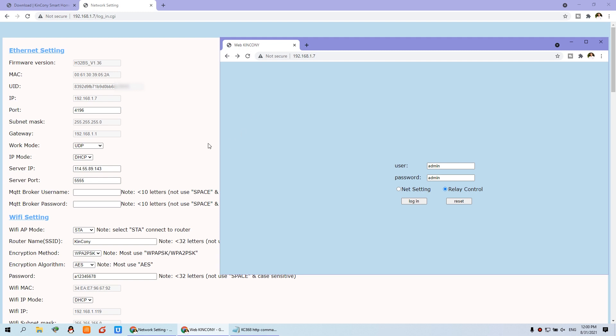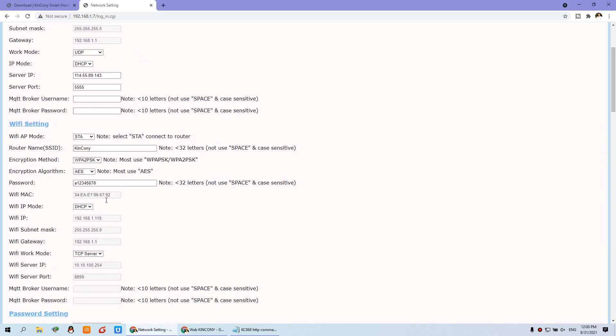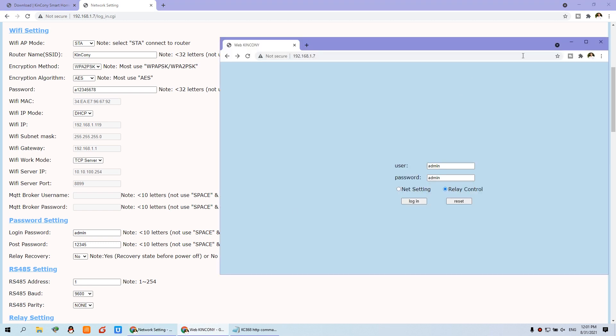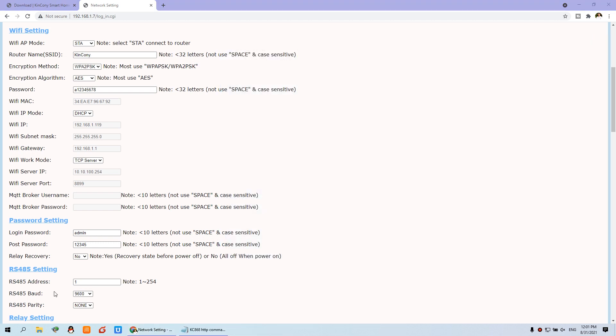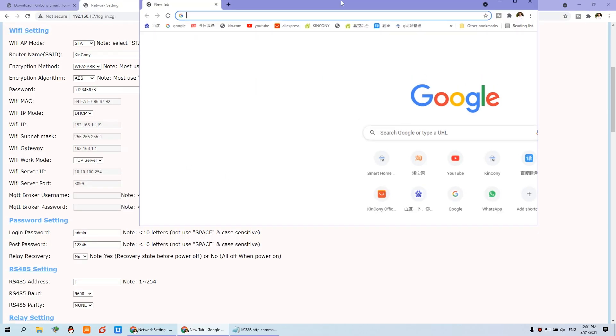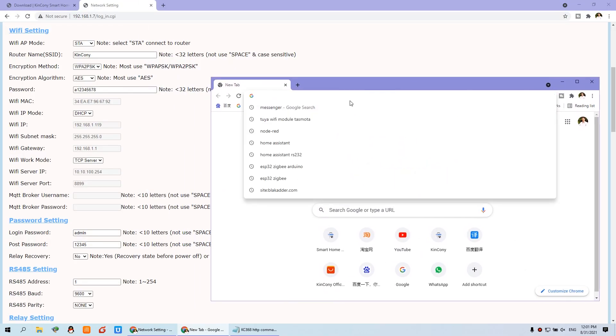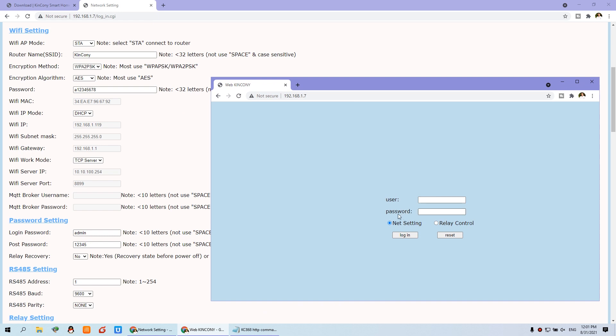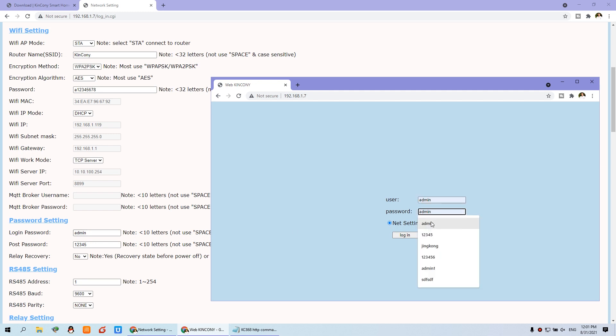Before we can send a command, you can see here are some settings you need to understand: the password. This is the login password and this is the POST password. The login password means when you open this web browser and input the IP of the controller, you will see a username and password prompt. The username is always admin, and the password is the login password.